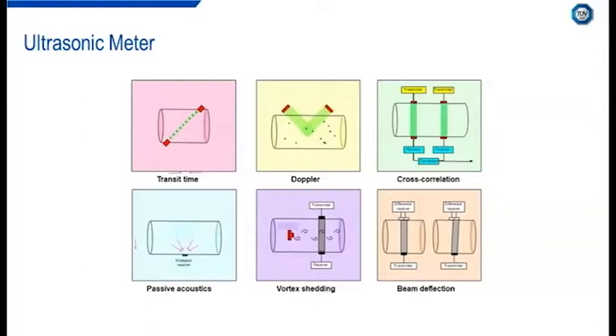Depending on the application and type of ultrasonic metering technology selected, the transducers can be arranged in different ways. The capability of non-invasive measurement is a benefit and advantage for the ultrasonic meter when compared to traditional metering technologies. They also have no mechanically moving parts, which is another advantage, as they are therefore not susceptible to damage. Ultrasonic meters do require a well-developed velocity profile for optimal performance, and again, 30 diameters of straight piping upstream is recommended as a minimum when using an ultrasonic flow meter, although a flow straightener could be used or considered as well for optimal performance. Ultrasonic meters are available for liquid and gas applications.